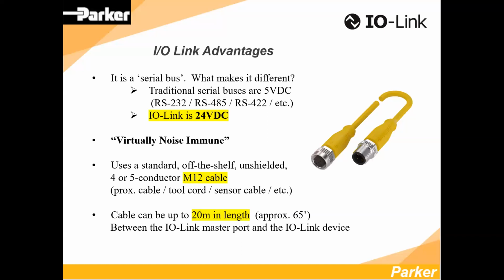More IOLink advantages - again, it's a serial bus at a 24-volt level, and virtually noise immune. The only applications I've run into that were a concern are welding applications, and not even resistance or spot welding - those cycles aren't long enough to interfere. But MIG and TIG type welding, or continuous welding applications, you have to be very concerned about separation between your welding or power cables and your low voltage or COM cables.